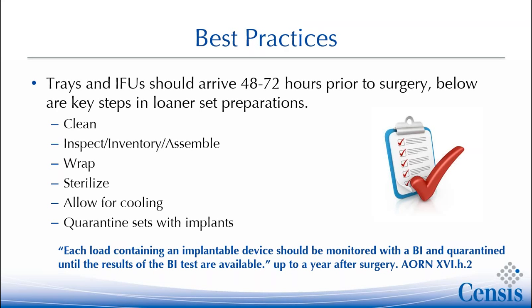There are key steps that you need to do in preparing the loaner tray. You have to clean it, inspect it and do your inventory. You have to assemble, or maybe disassemble, certain items in that tray. Then you're going to wrap it, or have it in a container, and sterilize it at the appropriate cycle time, remembering that not every tray may have the same cycle time. We can have cycle times from 4 to 40 minutes. So you have to know in your IFU what is required from the manufacturer that provided that tray to you.